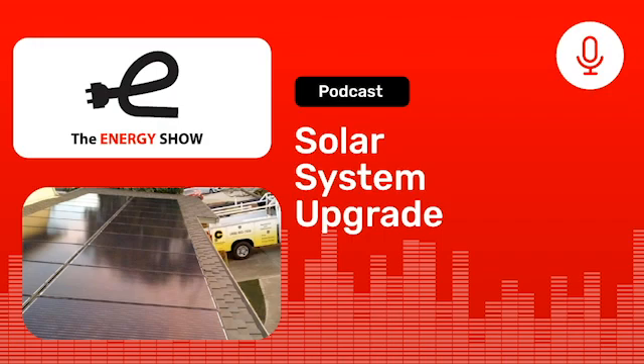In terms of these DC coupled systems, the most popular manufacturer is SolarEdge. There's others on display at the SPI, Solar Power International show in October. But SolarEdge is the market leader, although there are other companies that are starting to nip at their heels. So in terms of adding battery storage, if you have an existing SolarEdge system, it's pretty darn easy to swap out the old non-storage SolarEdge inverter and put in a new SolarEdge inverter. And as I said before, it's a good time to add more panels. This is usually a pretty straightforward swap. You don't really need to change the optimizers on the roof.